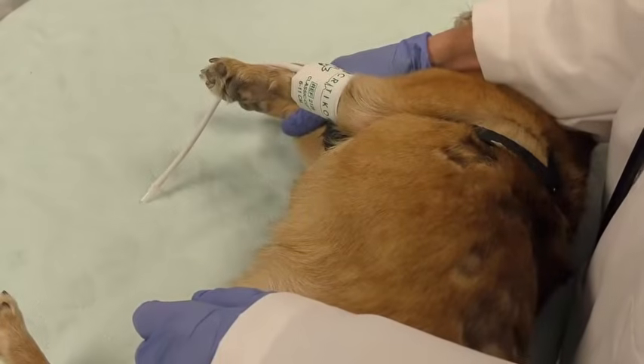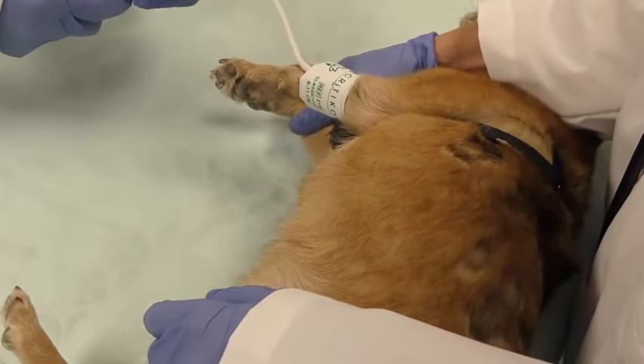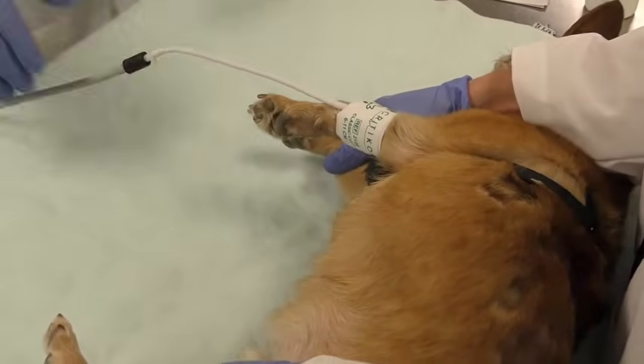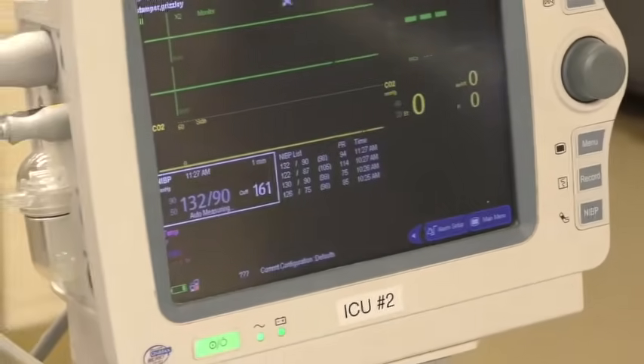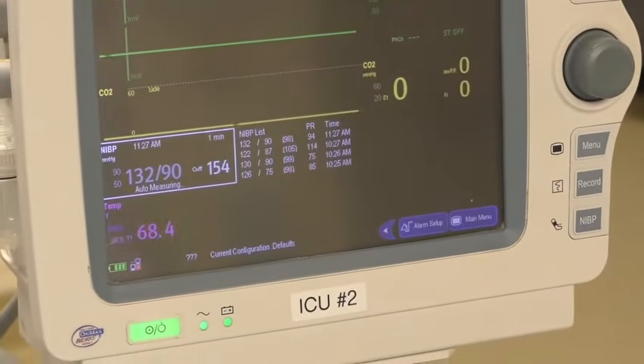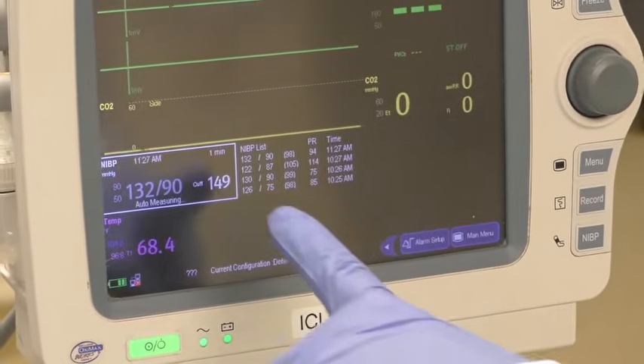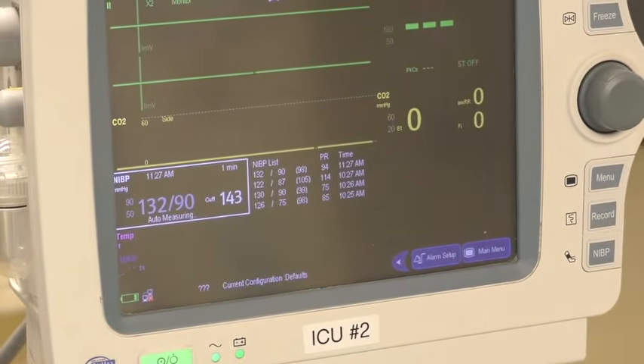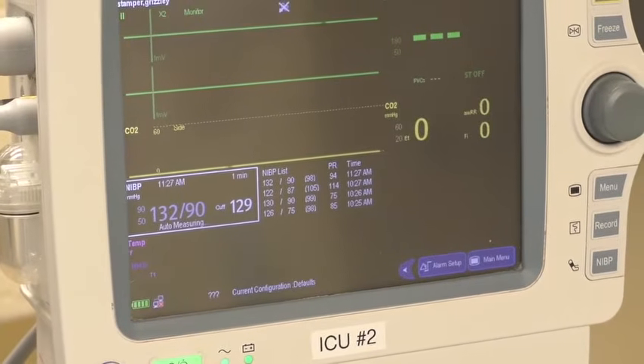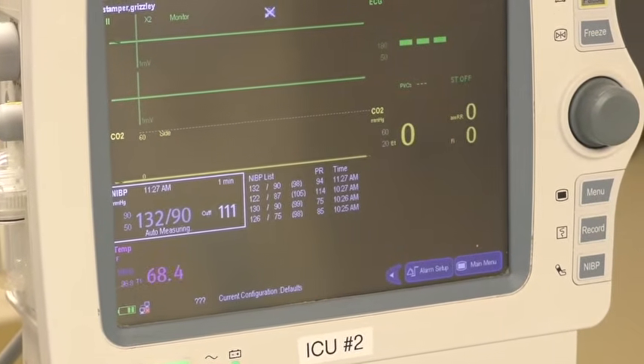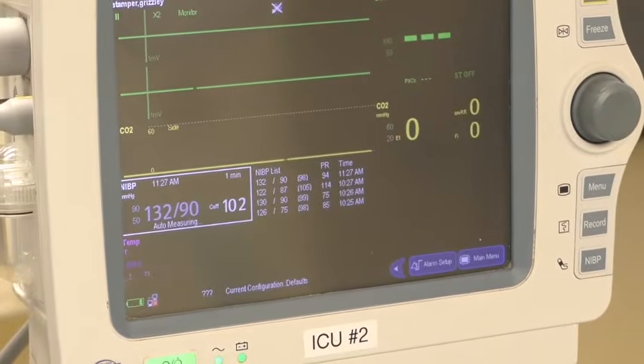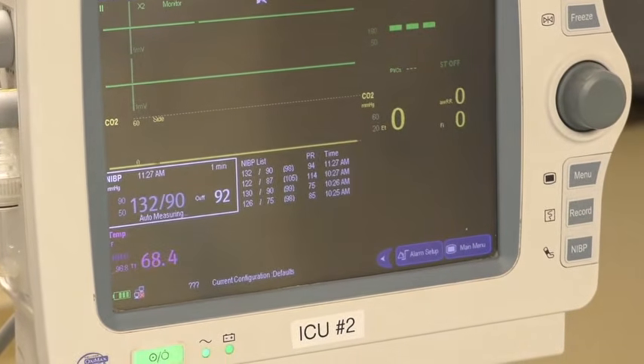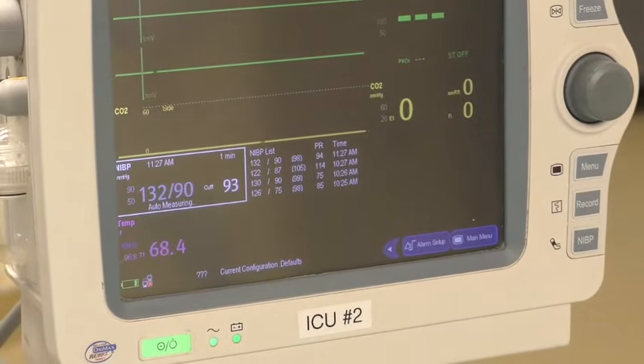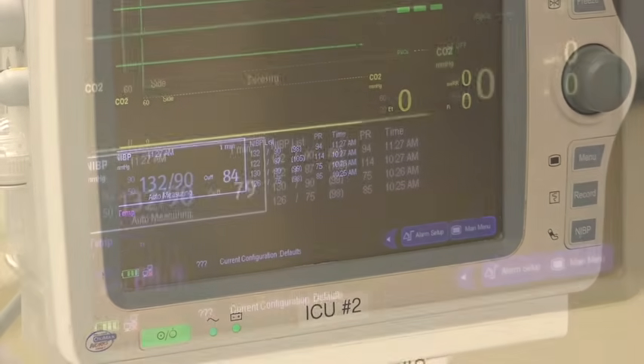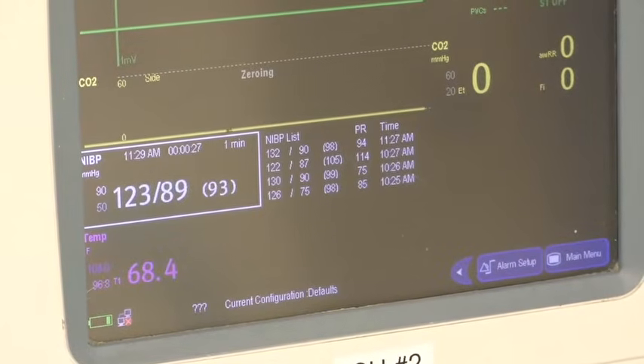The most reliable reading from the oscillometric blood pressure machine is the mean arterial pressure. When measuring, the oscillometric unit increases and decreases pressure in the cuff to first occlude the artery completely and then detect arterial wall oscillations induced by blood flow as the cuff pressure is released. The maximum arterial wall oscillation measured is the mean arterial pressure. The oscillometric device will then calculate the systolic and diastolic blood pressures based on the measured mean arterial pressure using an internal algorithm.